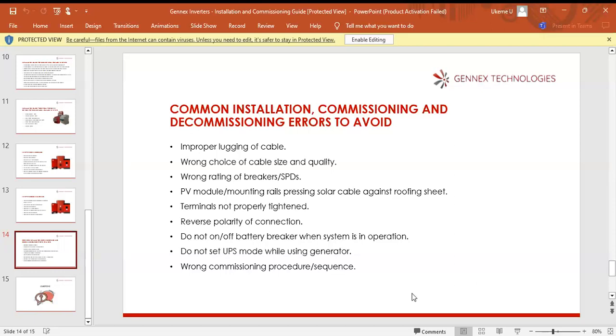Reverse polarity of connections will lead to instant damage of the system. So do not switch the battery breaker on or off when the system is in operation, whether the system is batteryless or one that operates on battery. If you want to change from battery to batteryless, shut down the system. It has to be deliberate. If I want to operate on batteryless now, I have to shut down, switch off the battery breaker, and then start it again. Not just anybody going to switch the battery breaker off or on anyhow. It could lead to a malfunction of the inverter and it could even get it damaged. So reverse polarity of connections is not acceptable.